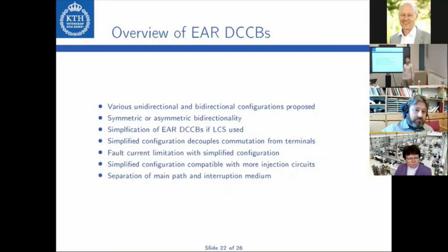A general advantage of the EAR DCCB is that it separates the main path from the interruption medium, in contrast to current injection DCCBs. This means that the mechanical switch in the main path never has to operate at relatively high current ratings like 9 kiloamps. This allows the use of smaller mechanical switches, which can potentially be operated faster or with a simpler actuator. And as I told you, the mechanical switch is always the true bottleneck.